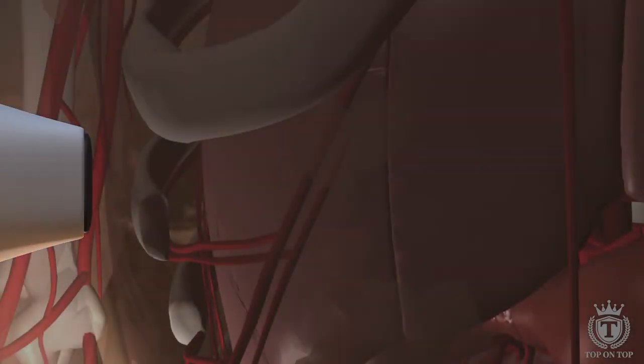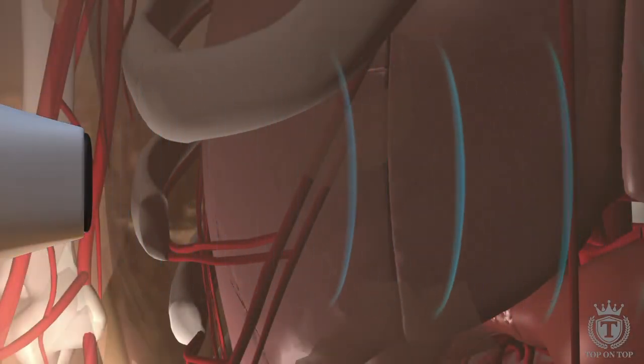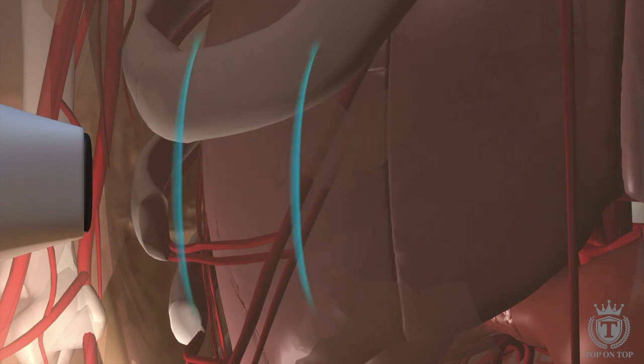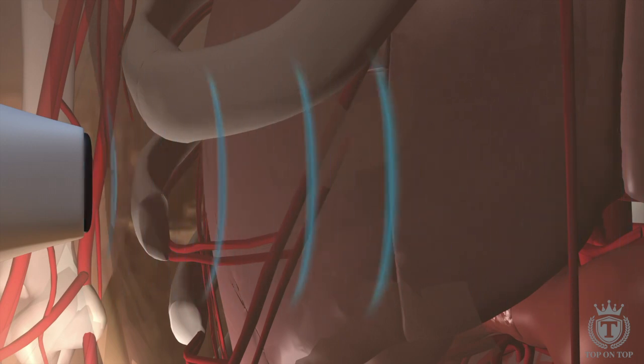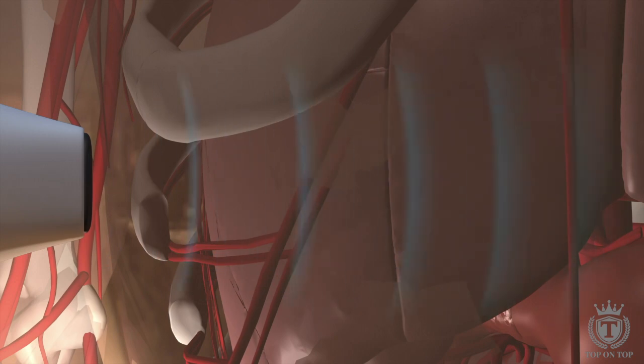More importantly, this type of crystal can also work in reverse. It can produce electrical signals when it detects high-frequency sound pressure waves. When a transducer directs ultrasound waves into the body, they pass right through the skin and into the internal anatomy. As the waves encounter tissues with different characteristics and densities, they produce echoes that reflect back to the piezoelectric crystal.